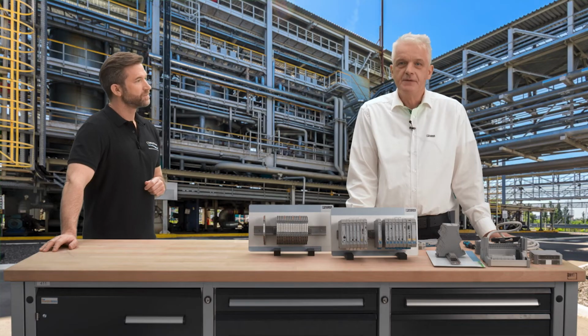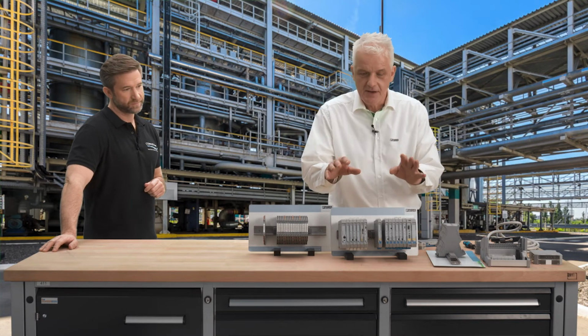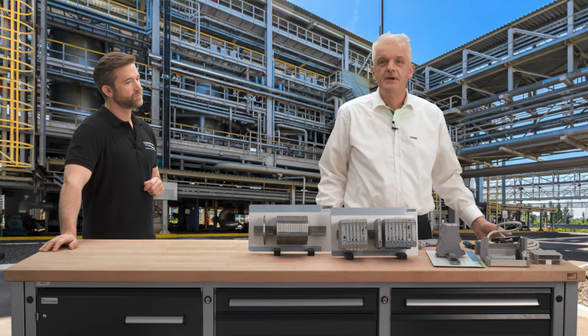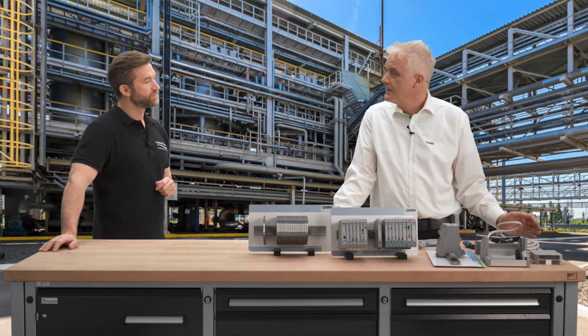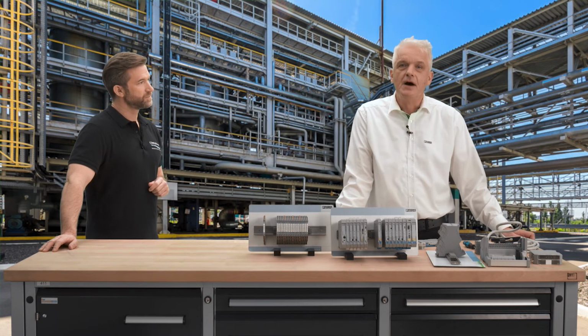If an MCR signal is part of a safety instrumented function, the system operator must carry out qualification of signal transmission with regard to availability and quality. Here the best choice would be the MACX Analog range. It has been developed for use in safety-oriented circuits in accordance with EN 61508 up to SIL 2 or SIL 3. If an intrinsically safe Ex i and possibly SIL solution is required, MACX Analog Ex is the best choice.